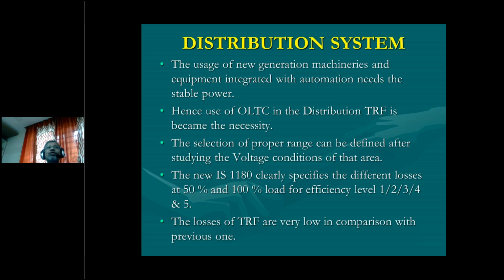Distribution system. The use of new generation machineries and equipment integrated with automation needs stable power. Hence the use of OLTC in the distribution transformer becomes necessary. The selection of proper range can be defined after studying the voltage conditions of that area. OLTC means on-load tap changer. Other normal transformers are OCTC, that is off circuit tap changers.